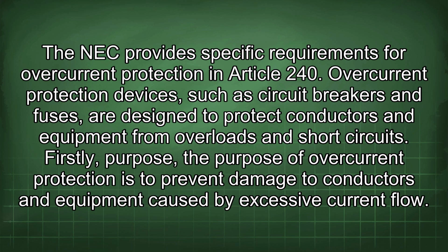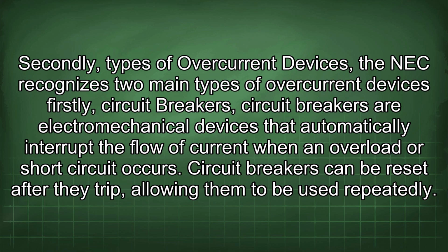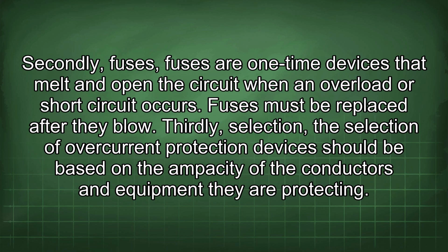Overcurrent protection devices, such as circuit breakers and fuses, are designed to protect conductors and equipment from overloads and short circuits. Firstly, purpose. The purpose of overcurrent protection is to prevent damage to conductors and equipment caused by excessive current flow. Secondly, types of overcurrent devices. The NEC recognizes two main types of overcurrent devices. Firstly, circuit breakers. Circuit breakers are electromechanical devices that automatically interrupt the flow of current when an overload or short circuit occurs. Circuit breakers can be reset after they trip, allowing them to be used repeatedly. Secondly, fuses. Fuses are one-time devices that melt and open the circuit when an overload or short circuit occurs. Fuses must be replaced after they blow.